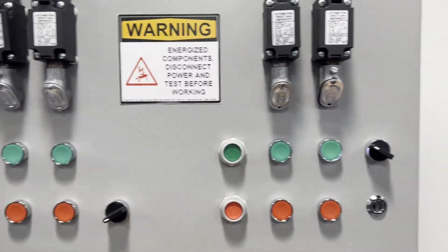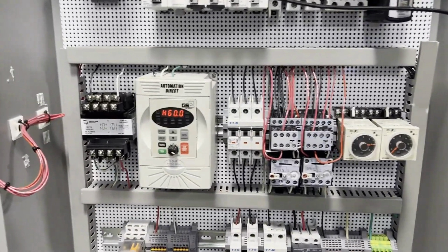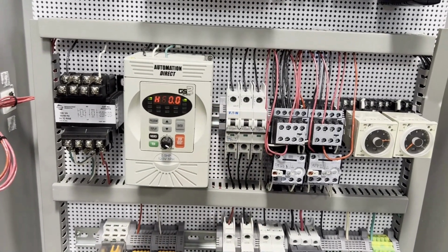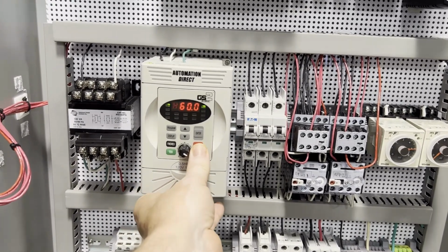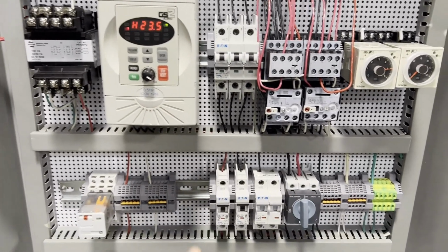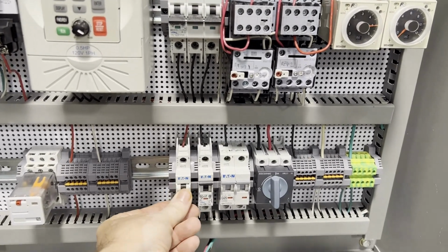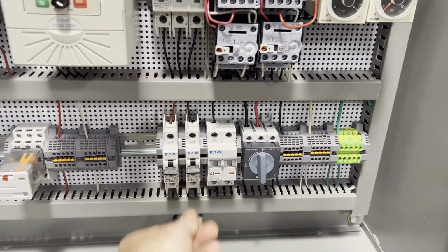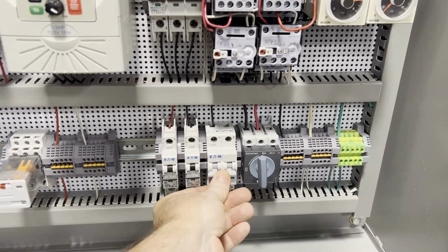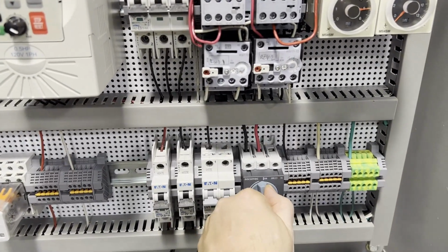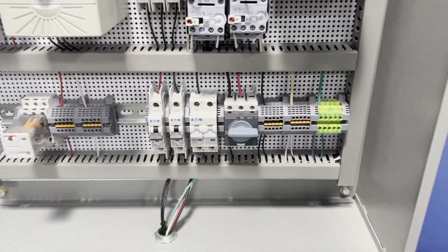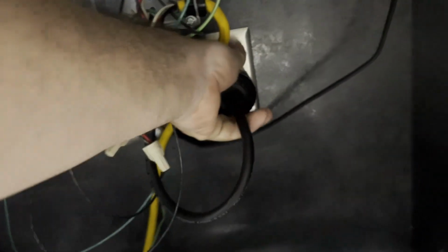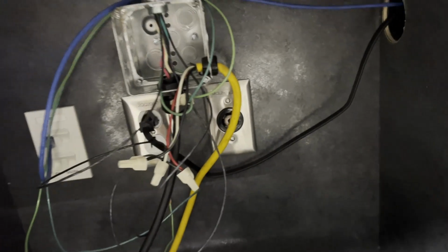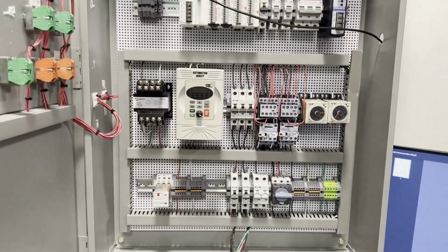Okay, we'll be securing power to the cabinet now. Starting out, 3-phase motor power, stopping the variable speed drive, securing the control power, securing the high voltage, combined circuit breaker. Right now it's only to the bottom, but it would be to the top if we had a PLC running. And then our disconnect switch. And finally, don't forget to pull the plug. And don't grab there, grab there. And power is now secured to our cabinet.